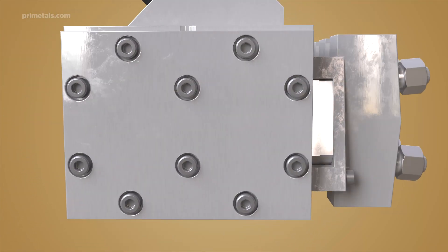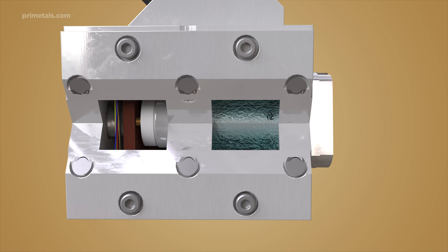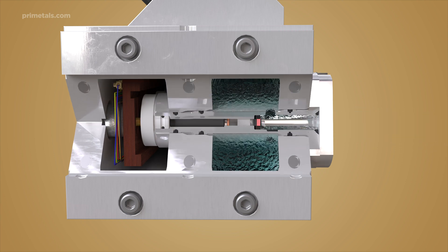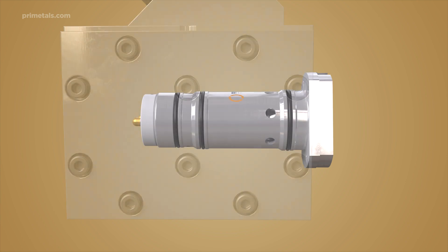The ISV adjusts coolant levels via pulse width modulation with each valve capable of dispensing 10 coolant levels. This enables controlled cooling in each zone. ISV systems connect to the mill's active flatness control to deliver coolant precisely where needed for flatness deviations.